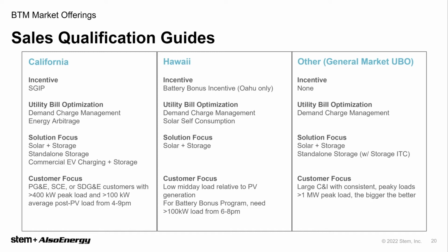To give you guys some perspective, the smallest system size that Stem currently sells is 500 kilowatt hours, and that's either 250 kilowatts or 125 kilowatts. That SKU is a great fit for a site with a 400 kilowatt peak load and a solar system of a comparable size.